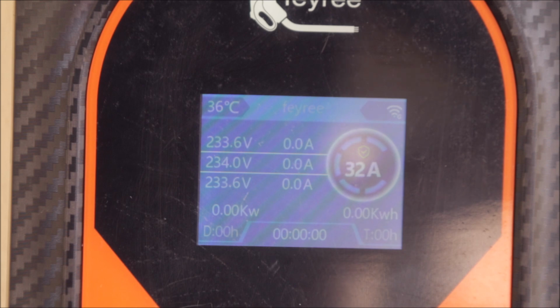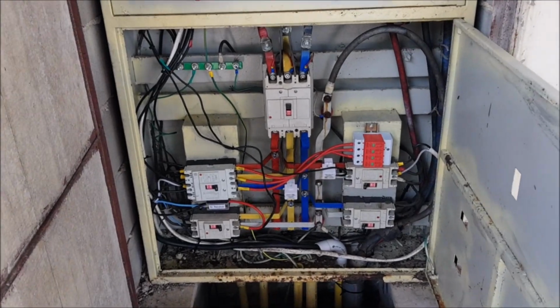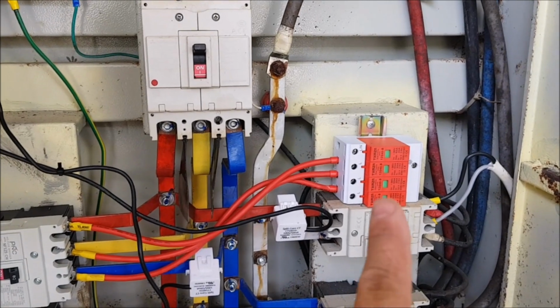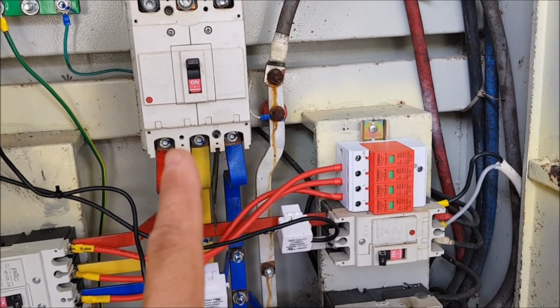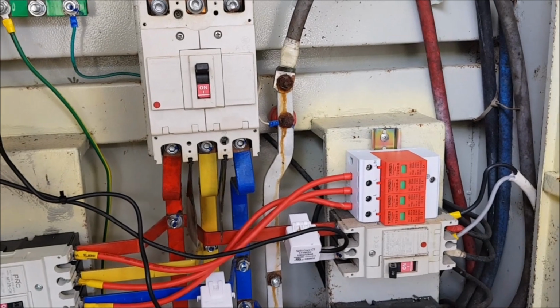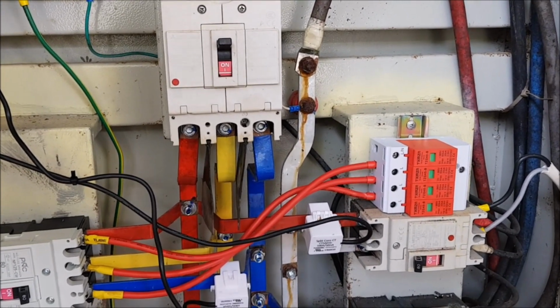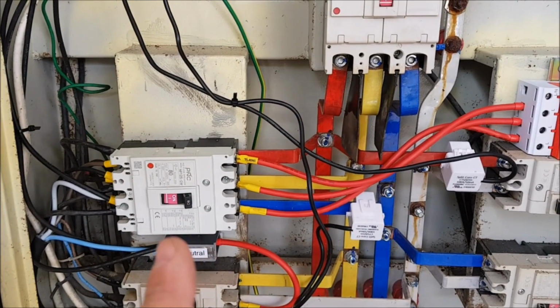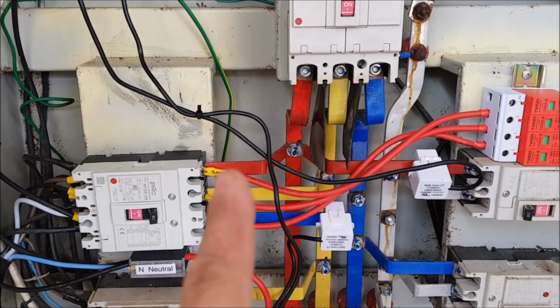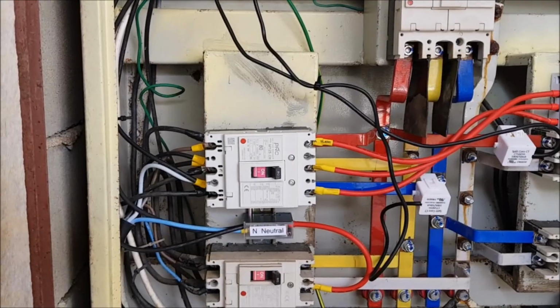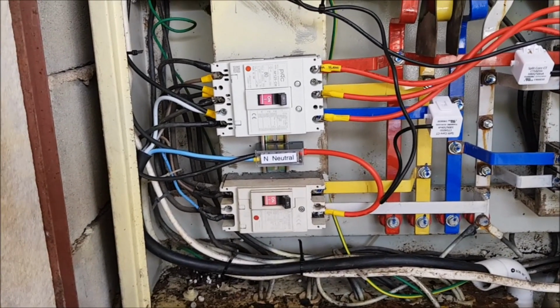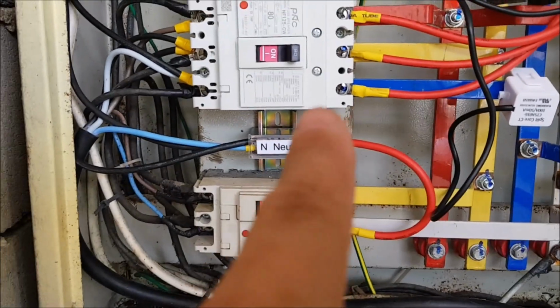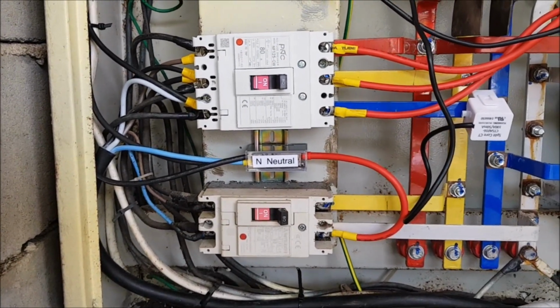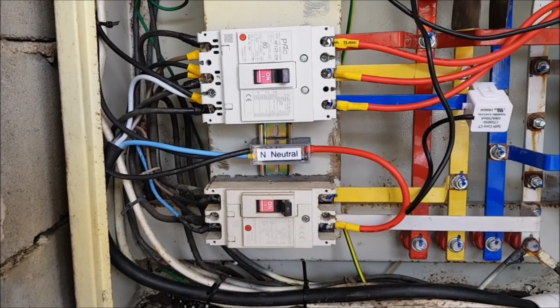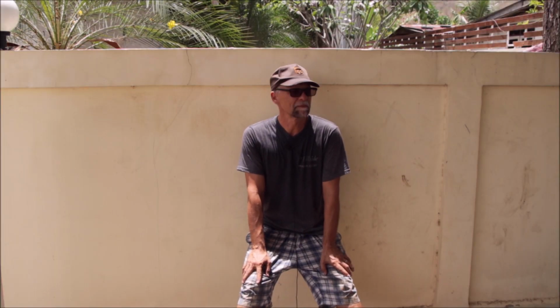So very nice. Let's take a look into the MDB, what has been done here. So I told you I have installed the surge protection. I wanted to connect it here on the main screws there on the bus there, but that was impossible to open those screws. So because I already replaced this breaker, I just connected them there. The new breaker, everything a little bit cleaned up there. Here the neutral bus bar, the new one, which is connecting a few things from the AC power wall as well. That was it for today.